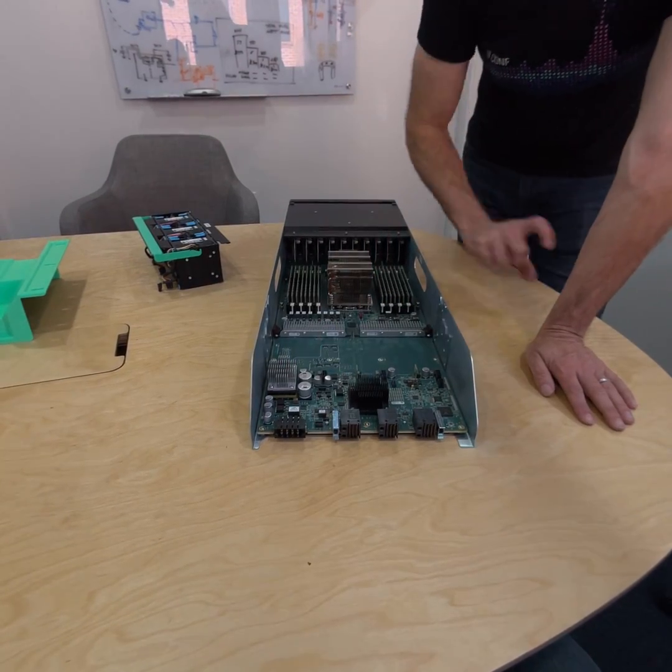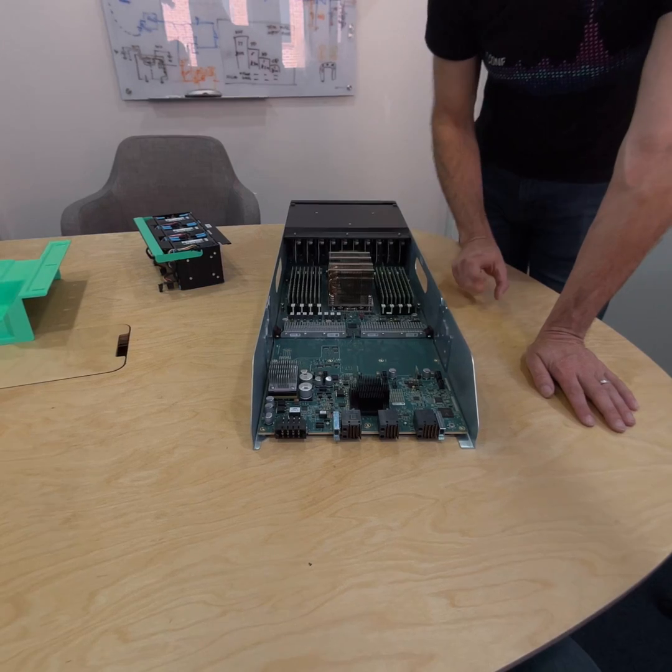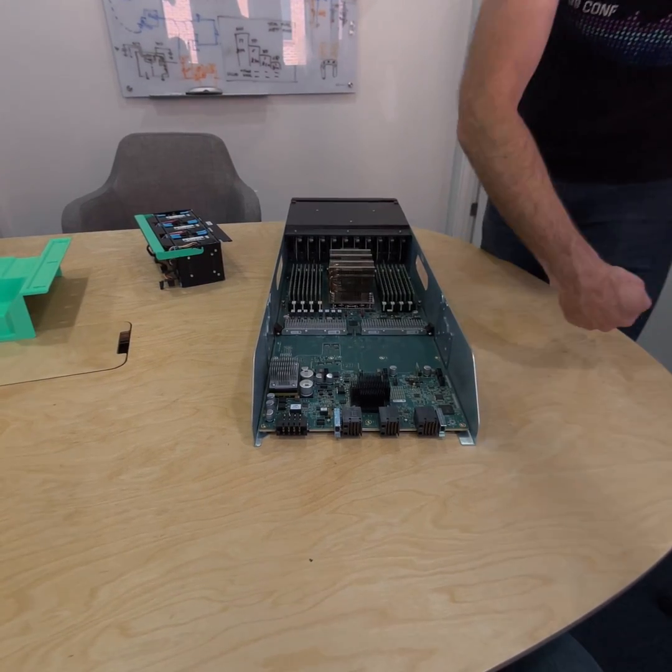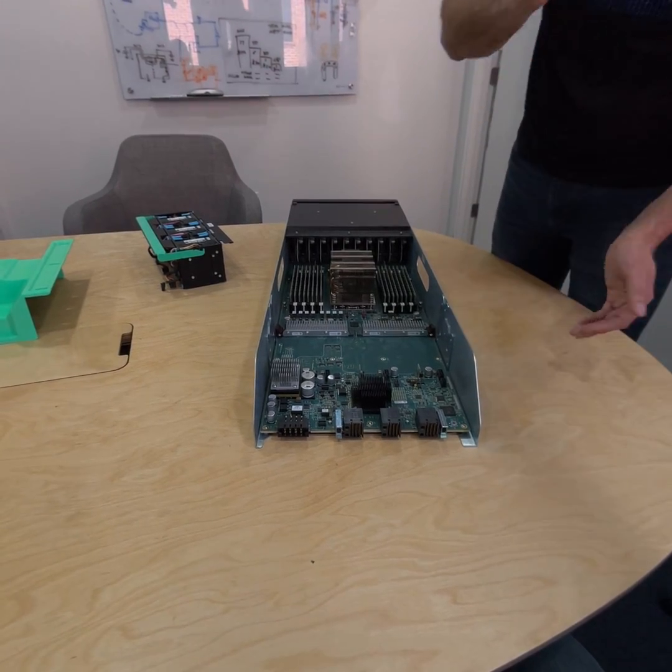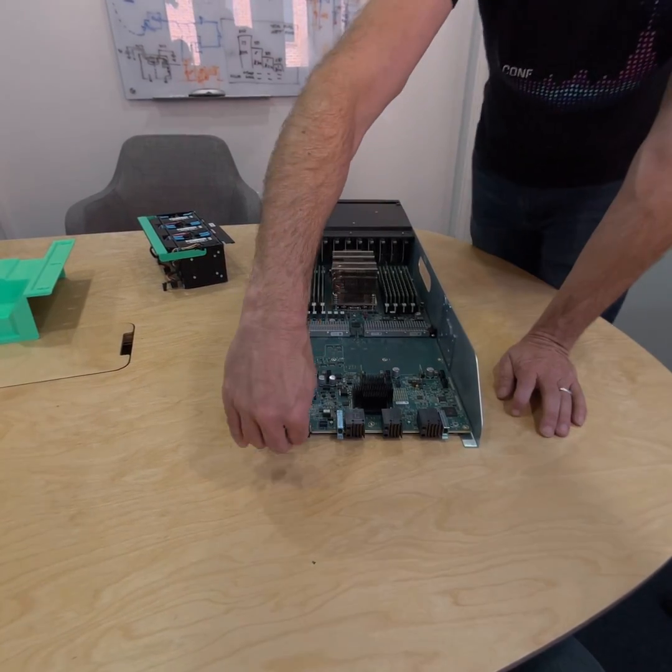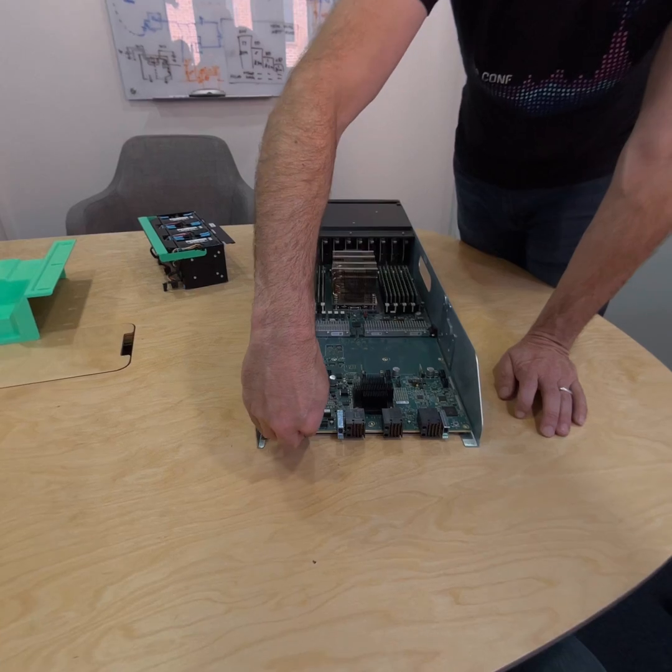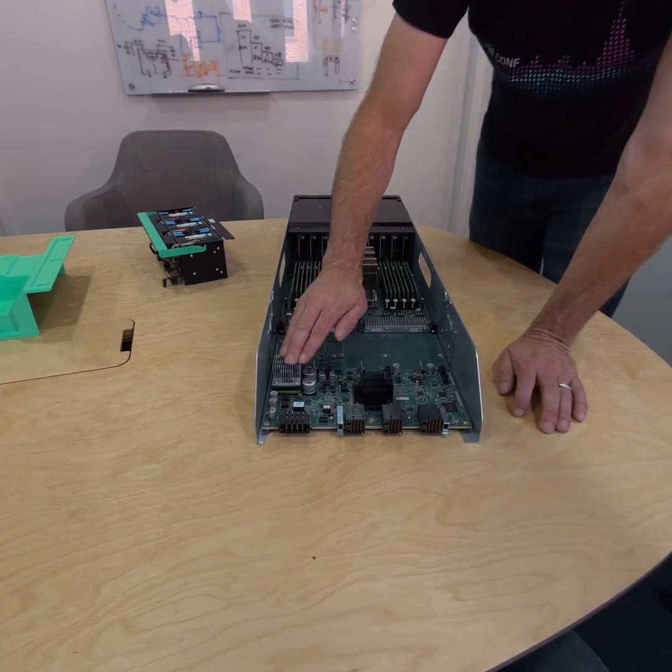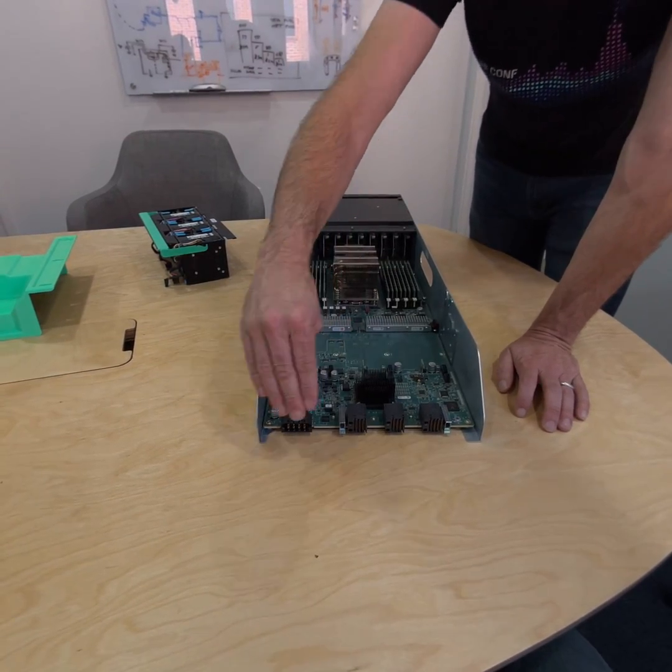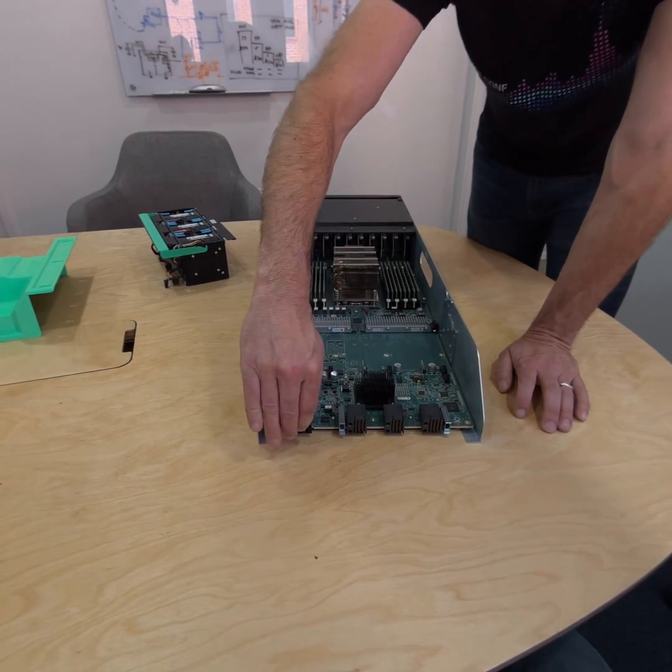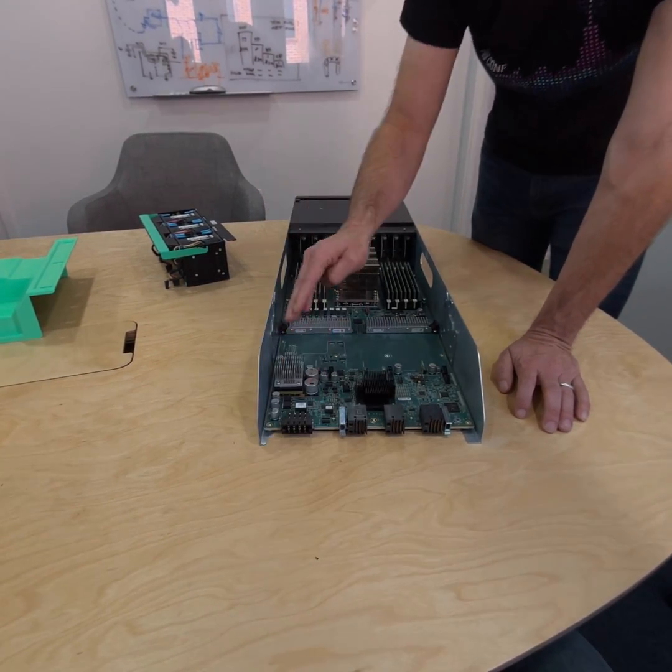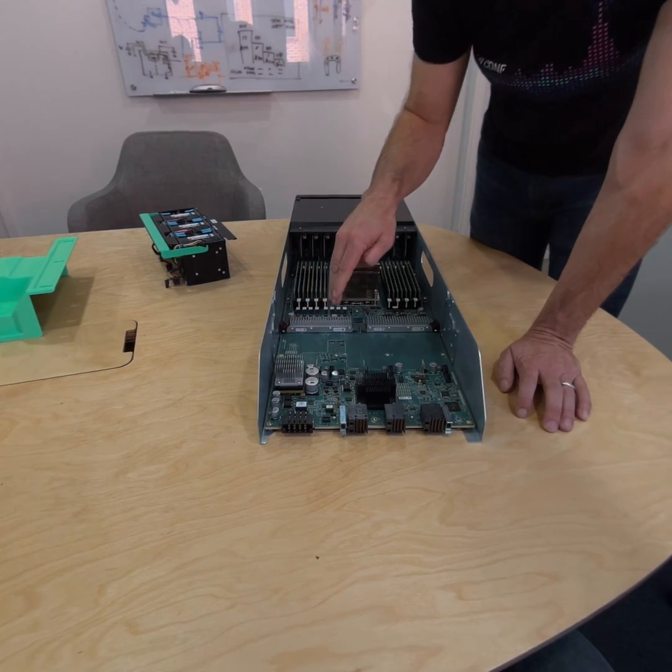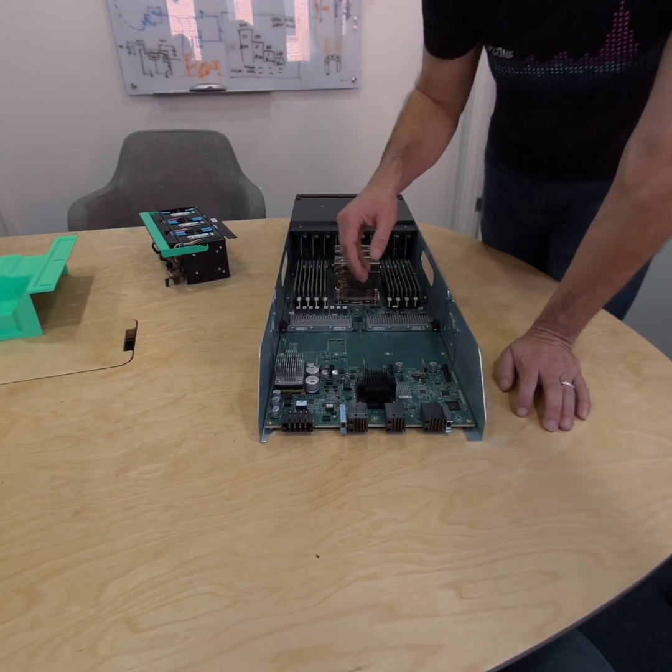We've got our rectifiers and our power shelf that are plugging in AC power there, turning it to DC. This is blind mating into that DC. We've got our bus converter here taking that from 54 volts on the bus bar down to the 12 volts that we use in the system.